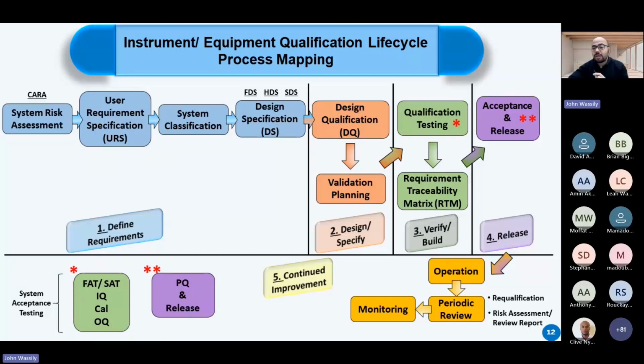The design qualification is about comparing the specifications that we requested in the URS document against the design specifications issued from the supplier side. By doing this comparison, we will make sure that all the requirements that we requested initially were actually fulfilled. And then we will go to the validation planning. The validation planning will rely on the system classification that we performed in the previous step. Based on the system classification, we will identify the qualification phases and the qualification testing to be performed. And we will see this together through the next slide.